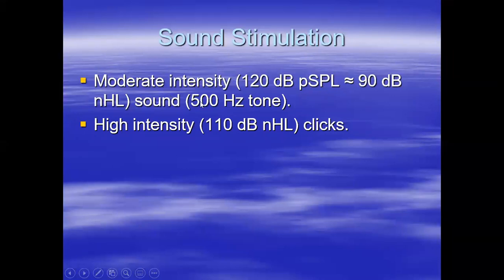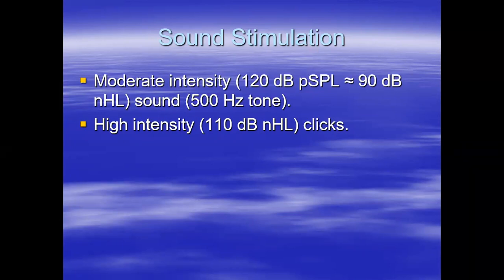You can use this sound intensity if you have the ability to stimulate at specific frequencies. There are dedicated VEMP systems on the market, but if you have a brainstem auditory evoked potential system in your laboratory, you can do vestibular evoked myogenic potentials on that as well — you do not necessarily need to buy a separate VEMP system. If you have a tone of 500 Hz, 90 dB above hearing threshold is sufficient. If you only have click stimulation, you need to go higher — to 110 dB.